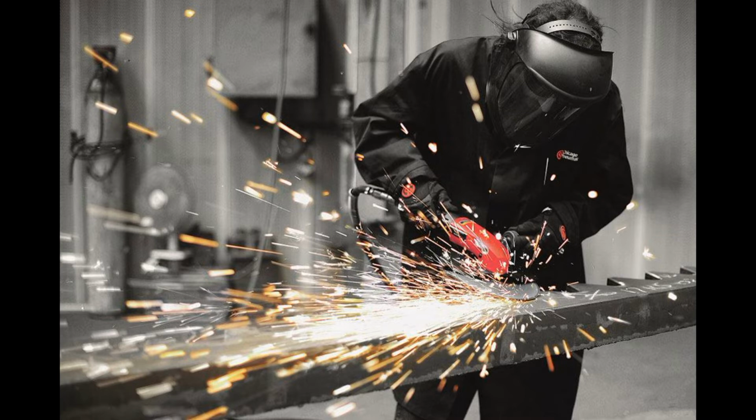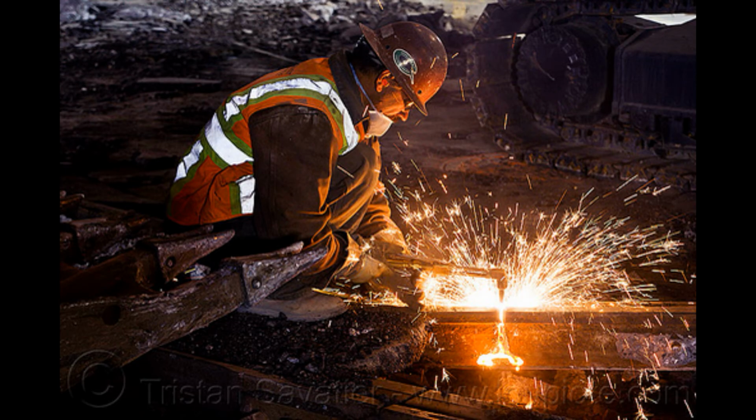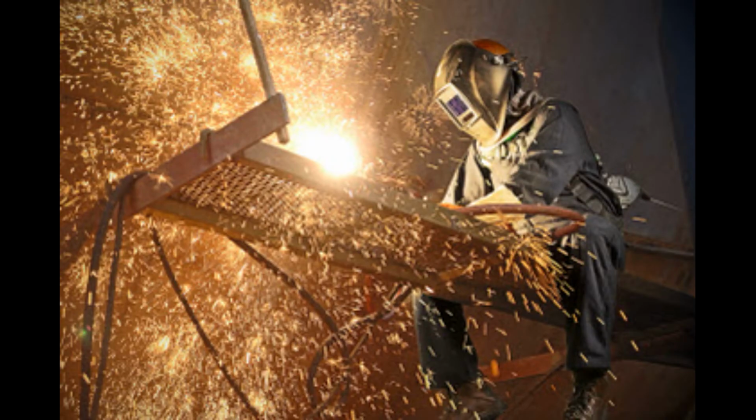There's been a question in the industry: how long should you actually stay there once the welding or the flames or sparks are completed? That is up to your GC, your company, your safety manual, whether it's 15 minutes, 20 minutes, 30 minutes. I've seen some companies that stay as far as an hour goes. But there definitely needs to be a wait period to make sure everything is cooled off. And I don't mean like a minute. I don't even mean like 5 minutes. Best practice is somewhere between 15 and 30 minutes. I've seen a re-spark happen up to 20 minutes later. So I'm pushing 30 minutes for the Safety Tavern, but again, talk to your competent person for flame and hot work.